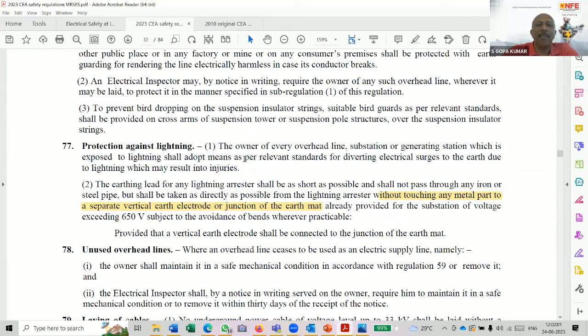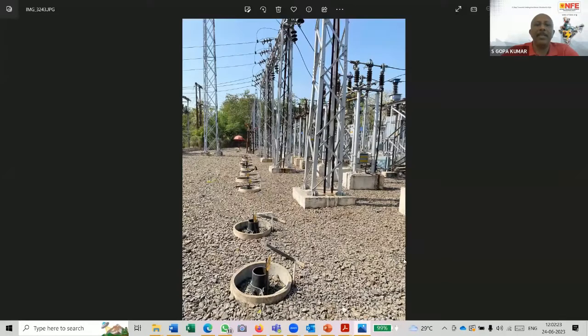The lightning arrestor shall be, this is applicable for more than 650 volt. That means an HT surge arrestor, as per the relevant standard, has to be connected. Now in paragraph number 2, which is highlighted, it says without touching any metal part, to a separate vertical earth electrode or junction of the earth mat. Practically what happens is, I'll show you a picture from a substation.